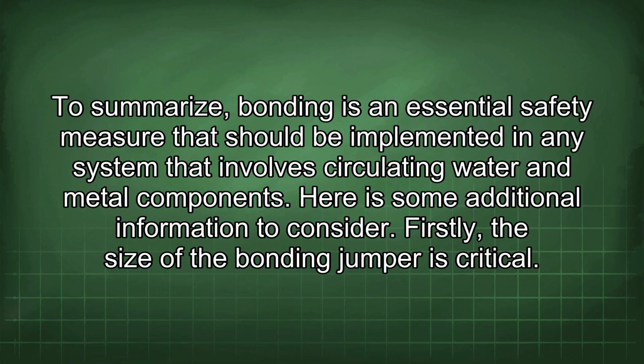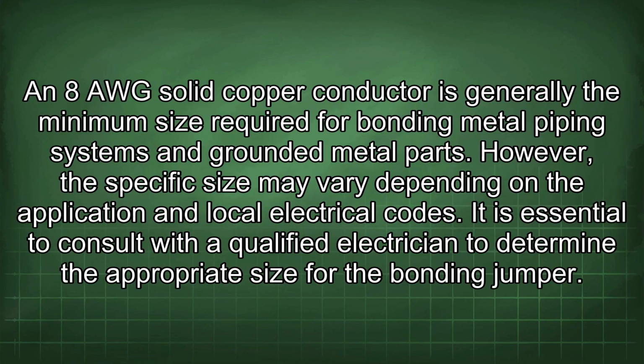Firstly, the size of the bonding jumper is critical. An 8 AWG solid copper conductor is generally the minimum size required for bonding metal piping systems and grounded metal parts. However, the specific size may vary depending on the application and local electrical codes. It is essential to consult with a qualified electrician to determine the appropriate size for the bonding jumper.